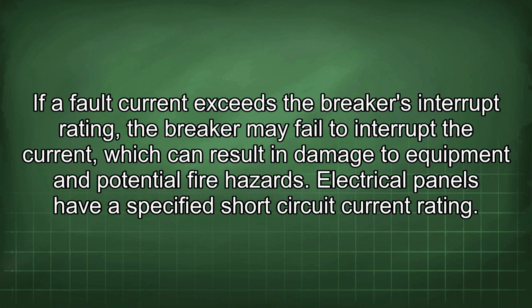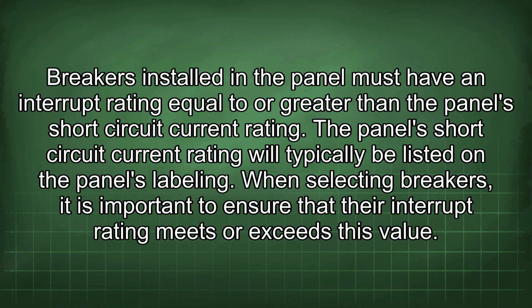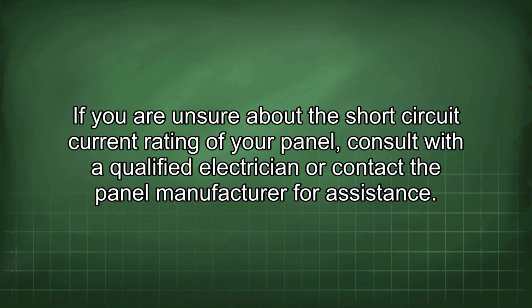Electrical panels have a specified short circuit current rating. Breakers installed in the panel must have an interrupt rating equal to or greater than the panel short circuit current rating. The panel short circuit current rating will typically be listed on the panel's labeling. When selecting breakers, it is important to ensure that their interrupt rating meets or exceeds this value. If you are unsure about the short circuit current rating of your panel, consult with a qualified electrician or contact the panel manufacturer for assistance.